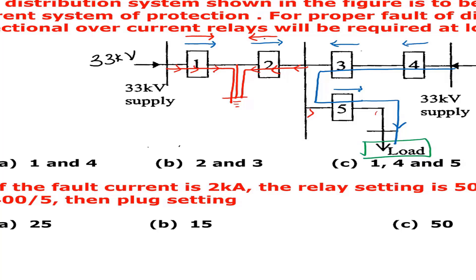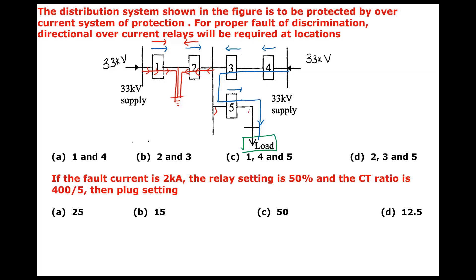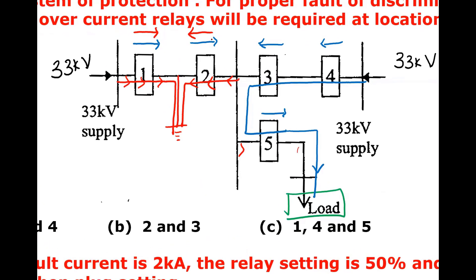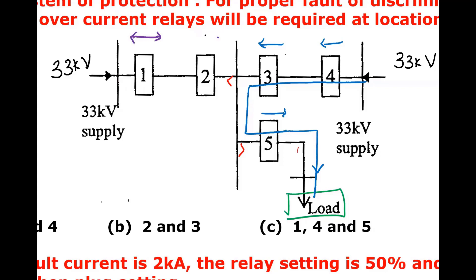This will help decide which should be non-directional and which should be directional. When both the normal current and fault current directions are the same, use a non-directional relay. When the normal current direction and fault current direction are opposite, use a directional relay set in the fault current direction. Relay 1 is non-directional and relay 2 is directional.